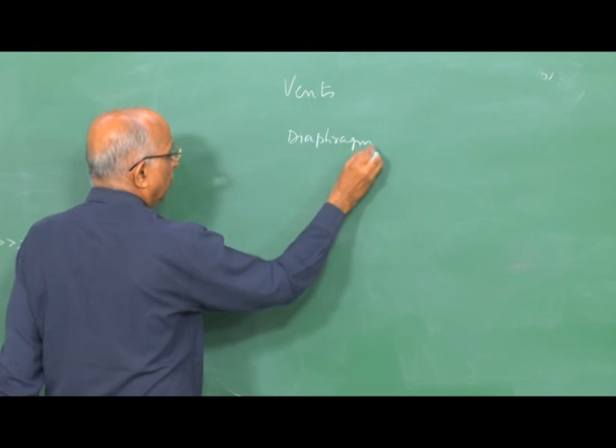Therefore, now the question comes, if I have a high value of dP by dt or a high value of PM, how do I control this? In practical cases, it is important for us to be able to restrict the maximum value of pressure and also control the rate of pressure rise. For that we use the following. In vessels of constant volume, we put vents, like we allow the gases to go out, or we put something like a diaphragm, which we call a burst diaphragm, or we have something like explosion doors. In other words, I have a volume over here, I put something like a burst diaphragm, which if the pressure exceeds some limit, goes away, and what is going to happen?